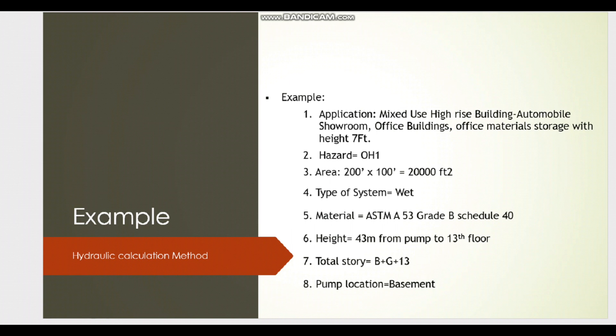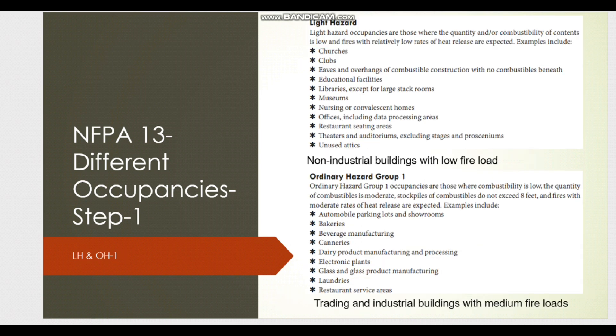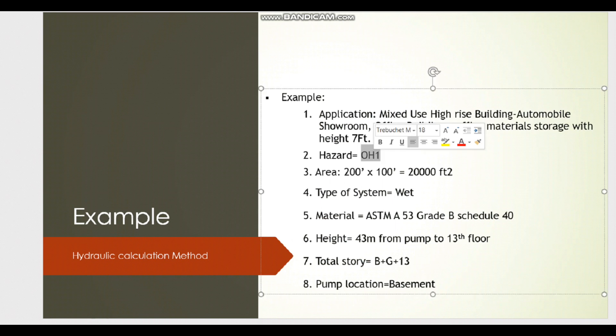From my earlier definitions, we have classifications like NFPA OH1 and OH2. In this case, the stockpile height does not exceed 12 feet, which would indicate NFPA OH2. However, since our storage height is 7 feet — which doesn't exceed 8 feet — we classify it as NFPA OH1. The automobile showroom also indicates SR1, and offices fall under light hazard, but the dominant classification is NFPA OH1.